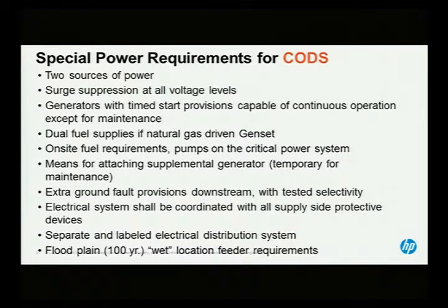If you're in a 100-year floodplain, all of your electrical installation has to conform to the wet code requirements. I would say if you're in a 500-year floodplain these days, you probably should meet that, and I'll let Hurricane Sandy speak for me on that one.